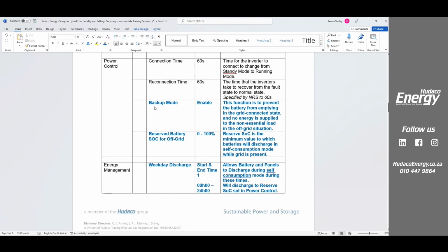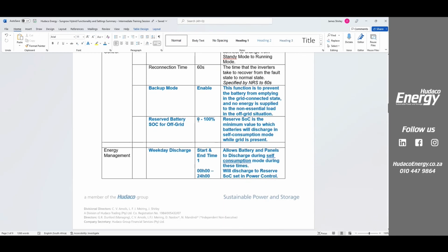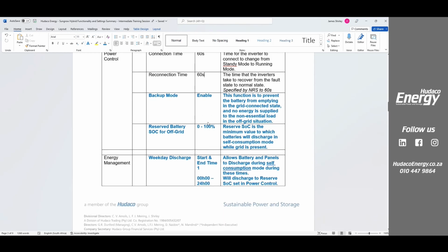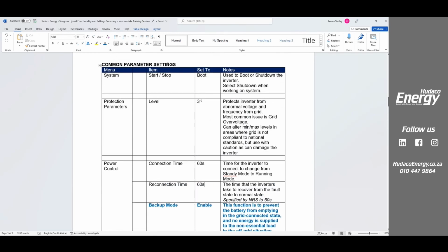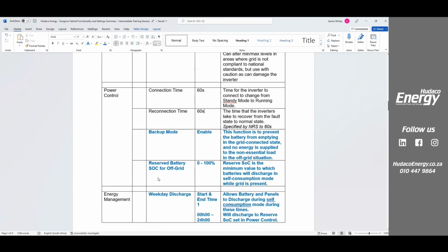Backup mode, we did this in the initial setting, but if it's not, you can turn it on and off here. So that should be enabled. And your reserve state of charge should be set at whatever you want it to be. The clients, the end users, in other words, the homeowner can control this, and this allows them to say, well, we know we're going into stage 5 load shedding. I want to set my reserve state of charge to 50%, or look, we haven't had load shedding for months now. I'm going to drop it all the way down to 10%, 15%, whatever it is, 20% of my batteries so that I can cycle and get the best return on investment from me.